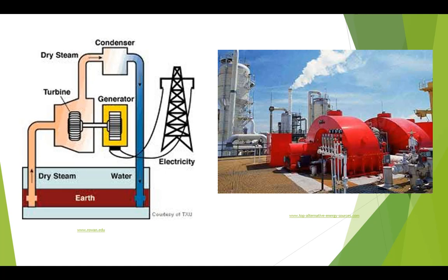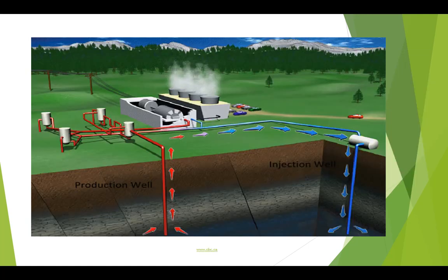From the turbine, the steam travels through a condenser and is often re-injected into the subterranean aquifer. These types of plants are less common due to the rare nature of suitable vapour-dominated resources. In a steam flash power plant, hot fluids reach the surface through a production well and are piped into a separator. The reduction in pressure causes some of the water to flash into steam, which is then fed through a turbine, condensed and re-injected for use again.